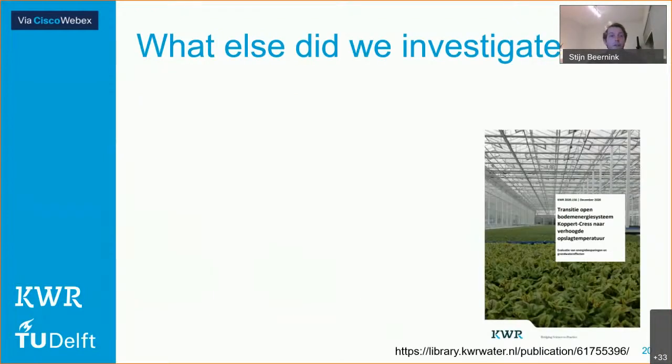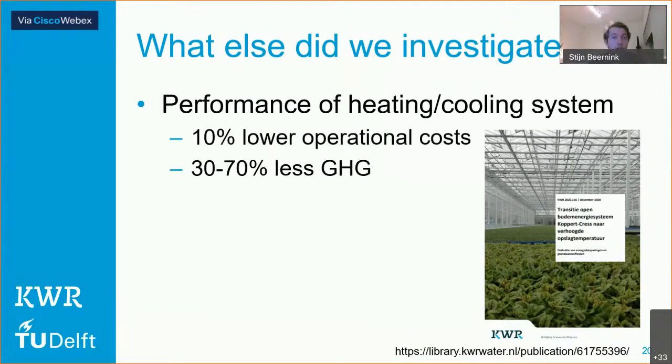However, this was not the only thing we looked at for this case study until now. We also looked, for instance, at the entire performance of the heating and cooling system with the higher storage temperatures. And we found that the operational cost decreased with 10% and that the greenhouse gas emissions decreased with even up to 30% to 70%.